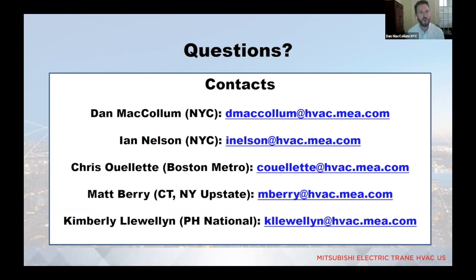Yeah, thank you. And actually, I don't know why you just made me think of this, but an interesting application I saw recently for the domestic hot water heat pump was just like we've done with our air source VRF condensing units. I saw an application where the QAHV domestic hot water heat pump was installed indoors. And the exhaust air from those units was used for another process in the building. I'm not exactly sure what they were cooling with it. Backing up to that heat recovery question, it's a kind of intricate way they came up with to do that.